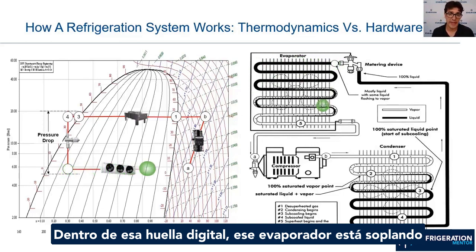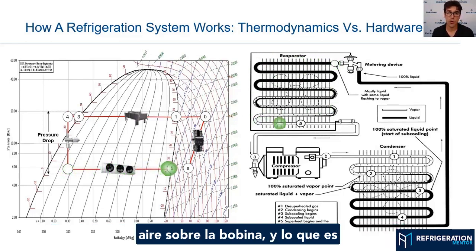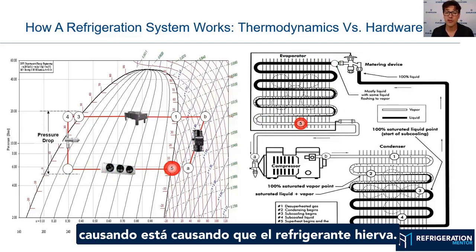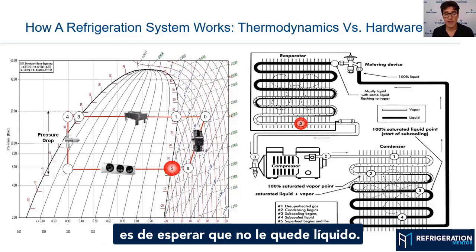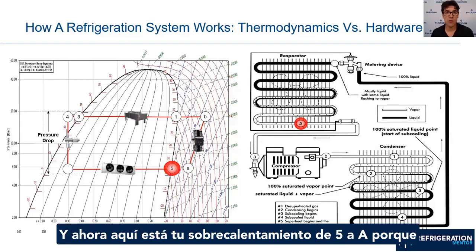As you can see, it just went through the metering device and now we're back into the 2-phase inside that thumbprint. That evaporator is blowing air over the coil, causing that refrigerant to boil. So by the time it hits that dew point again, you hopefully will have no liquid left.